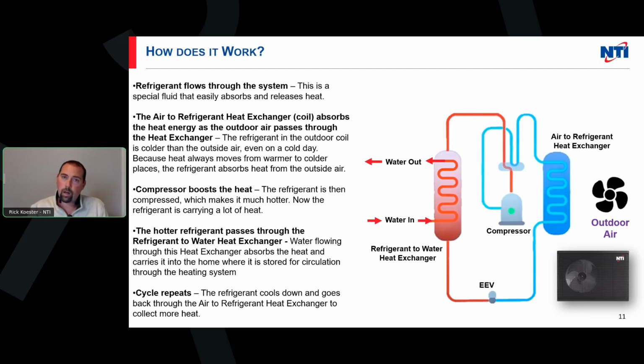So if we turn that fan on and start moving air through that large air to refrigerant heat exchanger, when that compressor kicks on and starts moving refrigerant through our system, as it goes through our metering device, or our expansion valve, we get a large pressure drop through this coil. If we drop pressure, we also drop temperature.